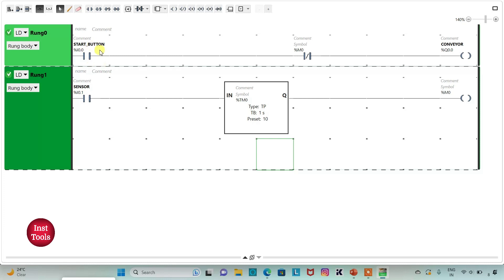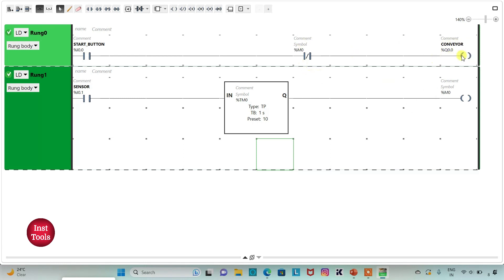So when I turn on the start button, the conveyor will get on. And then when the sensor gets activated — that is when the defective product is detected — the memory bit gets true for 10 seconds. And this memory bit turns off the conveyor. As the memory bit remains true for 10 seconds, the conveyor should also remain off for 10 seconds.